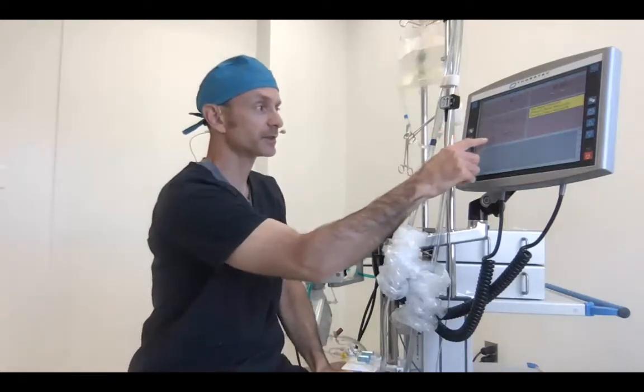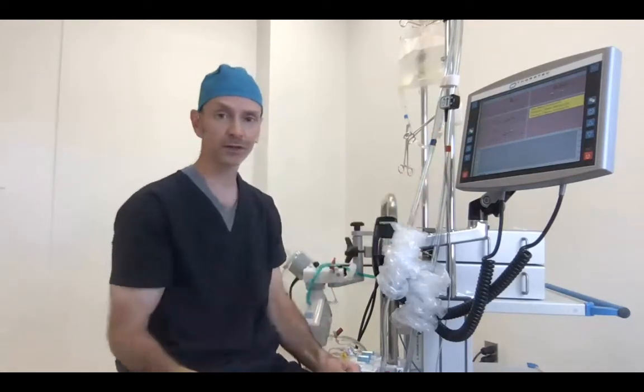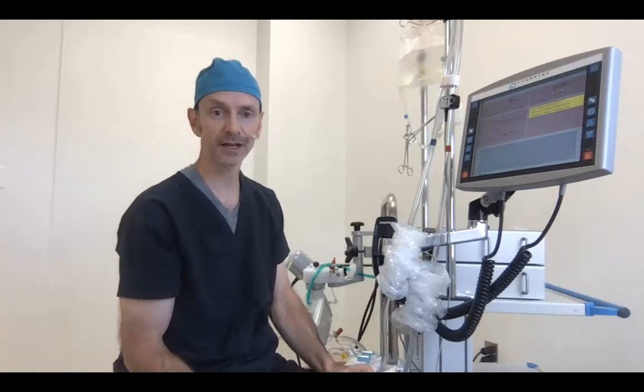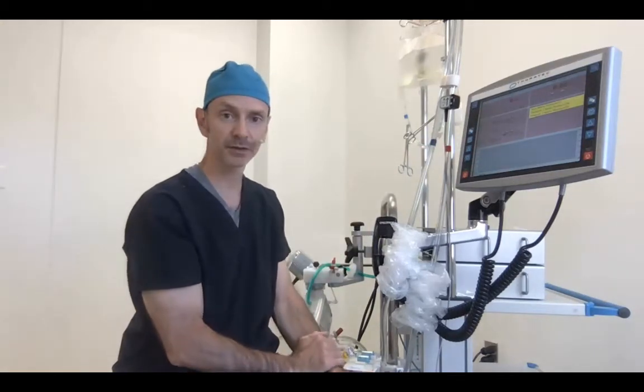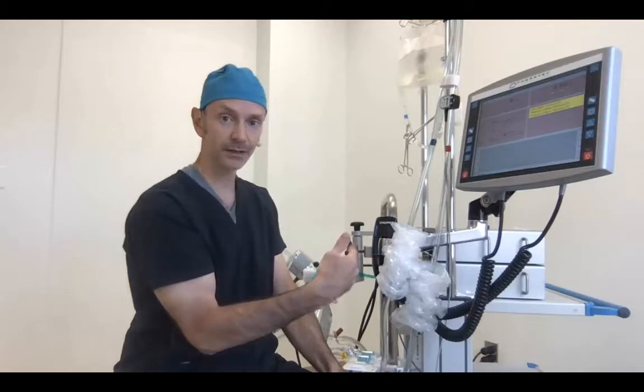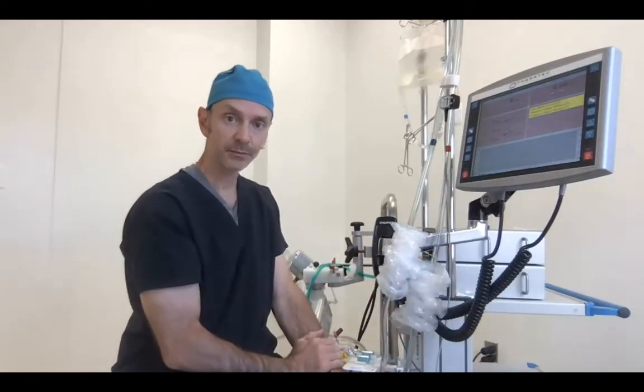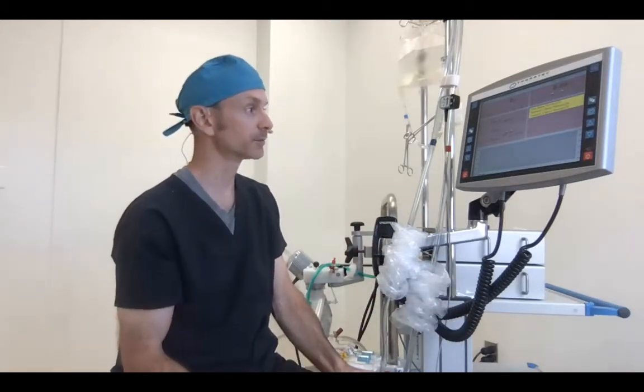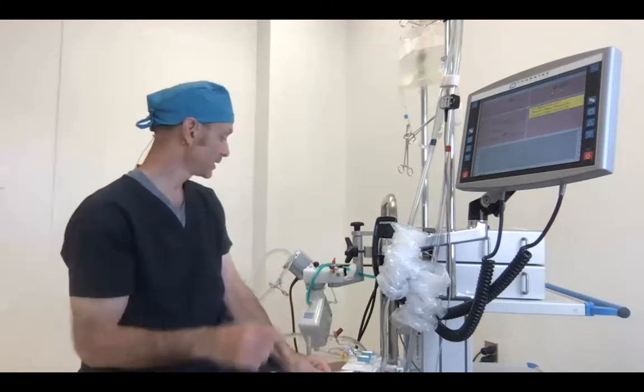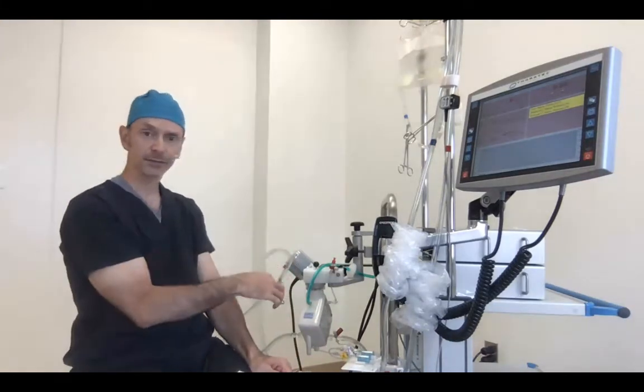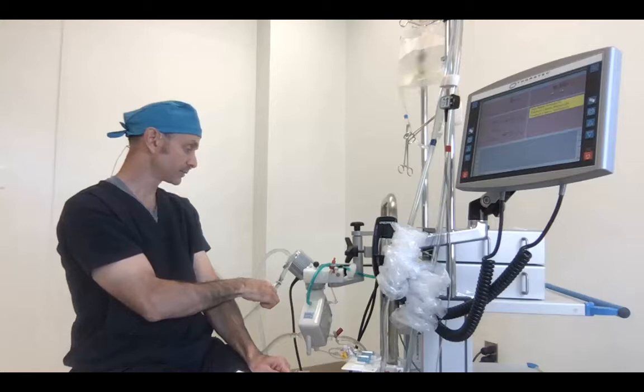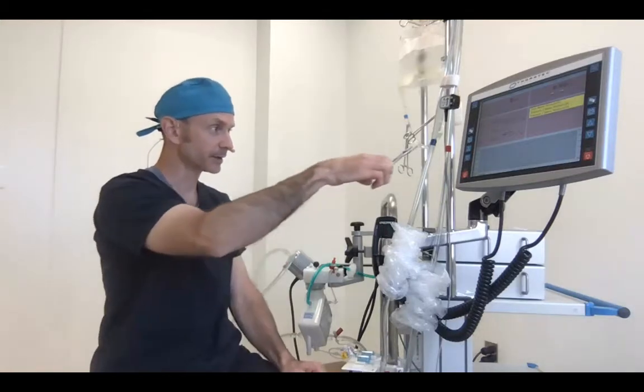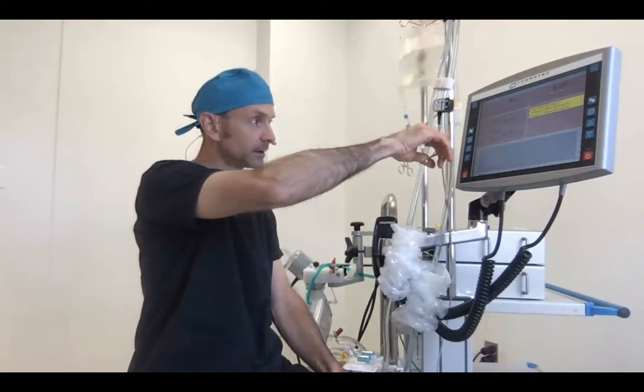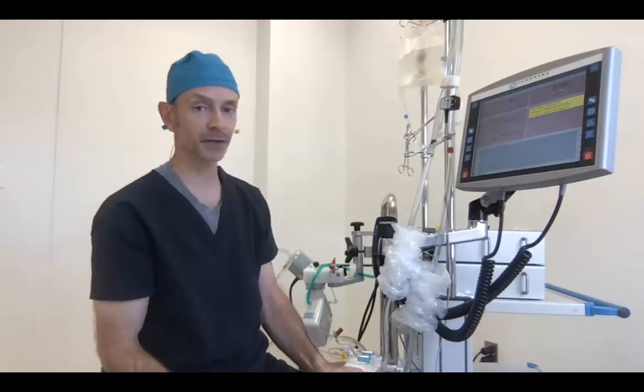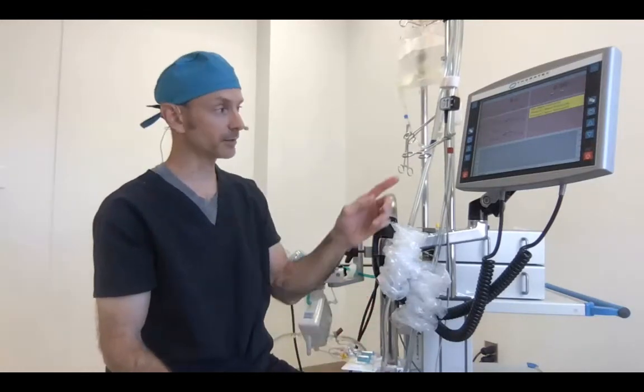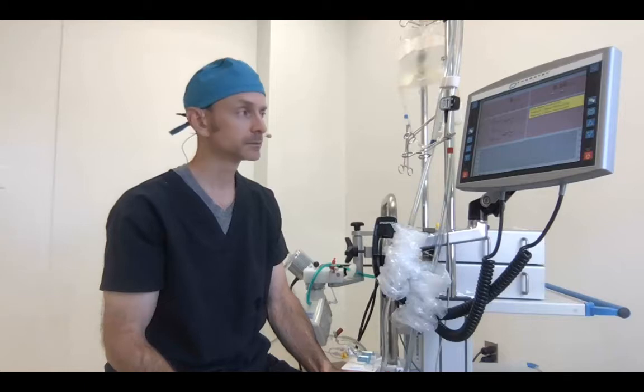And so this number of 72 and 71, let's say, for instance, we're initiating VA ECMO, and that is the patient's, that's what we're reading. That should be similar to the patient's arterial blood pressure. So if that's the arterial blood pressure, then what you would do is, with a clamp over on this side, you would increase your RPMs until you had a number greater than 72.